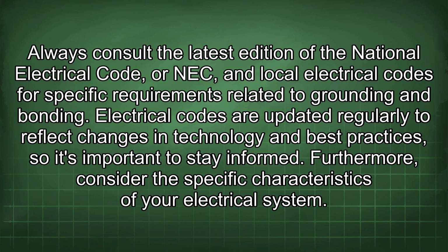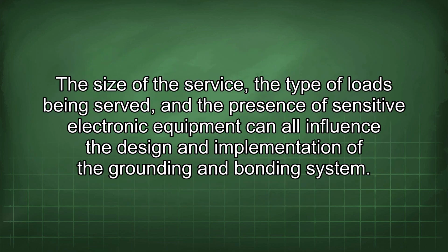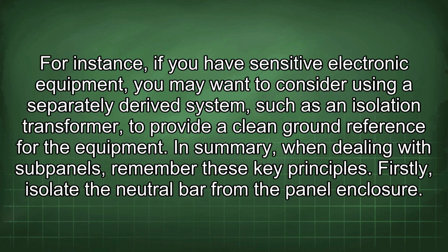Furthermore, consider the specific characteristics of your electrical system. The size of the service, the type of loads being served, and the presence of sensitive electronic equipment can all influence the design and implementation of the grounding and bonding system. For instance, if you have sensitive electronic equipment, you may want to consider using a separately derived system, such as an isolation transformer, to provide a clean ground reference for the equipment.